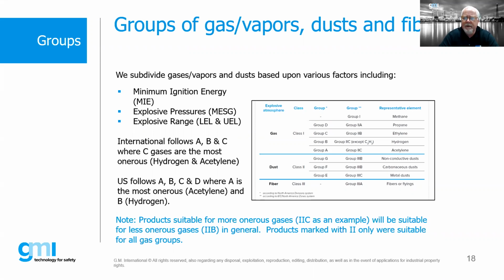So the gases that are most difficult to deal with are basically gases such as acetylene and hydrogen. And we put those gases, both from a North American standpoint as well as the international community, in pretty much an individual group. Most of the other gases and vapors will fall within other groups. But basically, looking at the international side of things, if it's below ground, a group 1 hazard, that is methane that we would typically find in a coal mine. But anything from a surface area, we would put in either a 2A, a 2B, or a 2C. So hydrogen and acetylene fall within 2C gas. Those are both 2C gases. Ethylene is a good example of a 2B gas, and propane is a good example of a 2A gas.